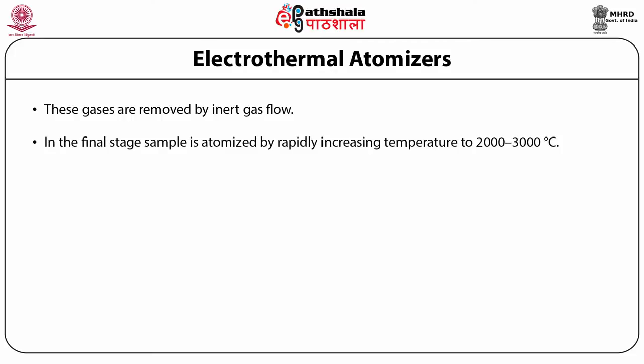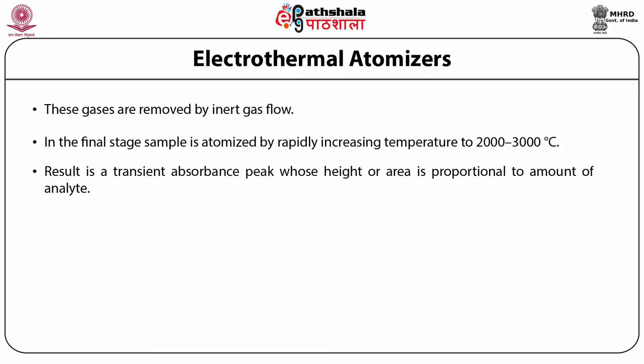In the final stage, the sample is atomized by rapidly increasing the temperature to 2000 to 3000°C. The result is a transient absorbance peak whose height or area is proportional to the absolute amount of analyte injected into the graphite tube. The three stages are complete in approximately 45 to 90 seconds, with most of this time used for drying and ashing the sample.